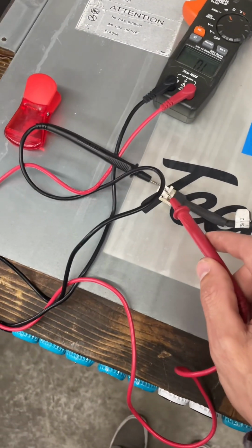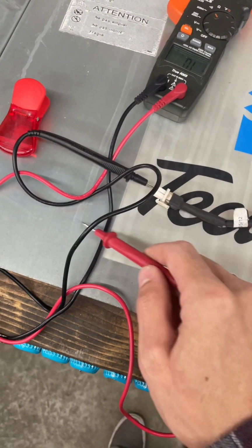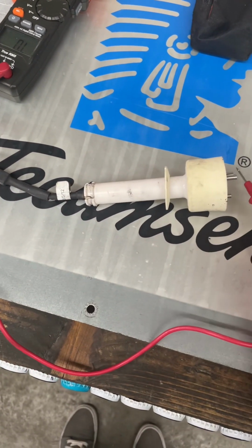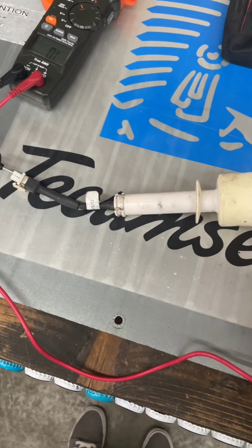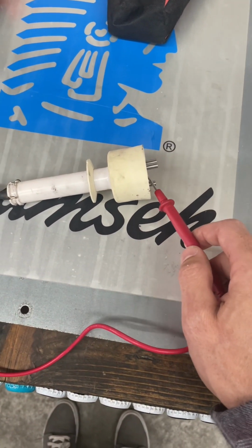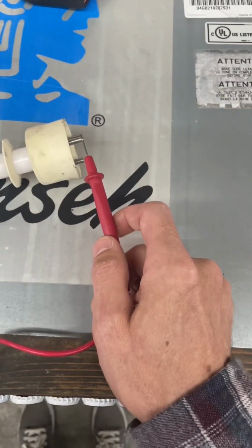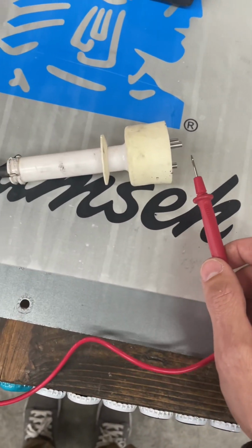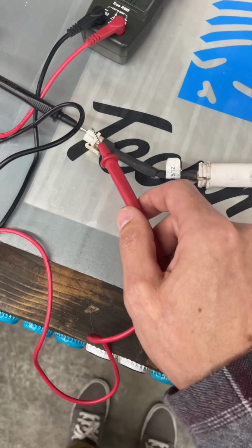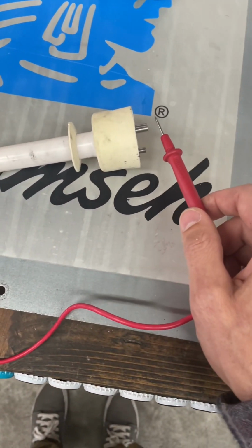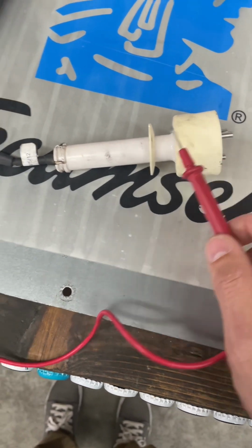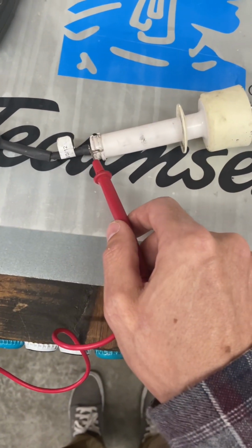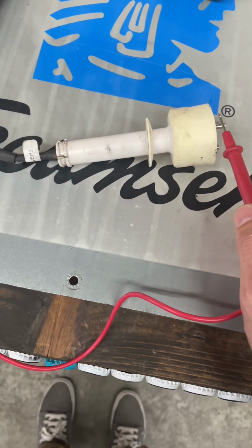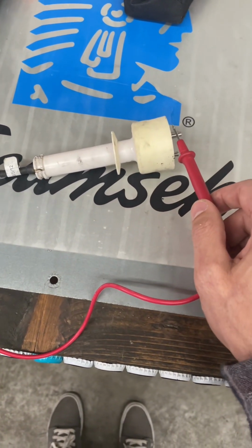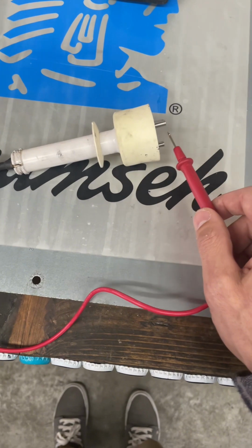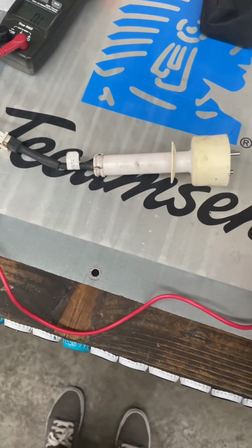And each one of the prongs on this plug-in should connect to only one of these posts. If for some reason you get a tone on two different posts for the same prong, that's a bad water level probe. If for some reason one of these prongs doesn't connect to any of these probes, bad water level probe. If this is a loose connection here and it's intermittent, sometimes you get a tone, sometimes you don't, bad water level probe. Luckily, this one is a good probe, and we're gonna go and put it in and see what happens.